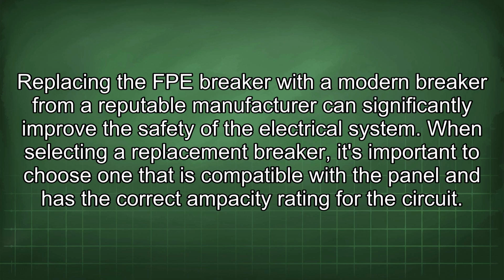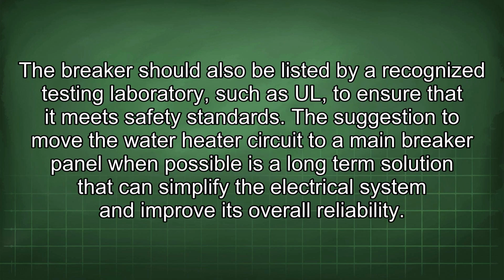When selecting a replacement breaker, it's important to choose one that is compatible with the panel and has the correct ampacity rating for the circuit. The breaker should also be listed by a recognized testing laboratory, such as UL, to ensure that it meets safety standards. The suggestion to move the water heater circuit to a main breaker panel, when possible, is a long-term solution that can simplify the electrical system and improve its overall reliability.